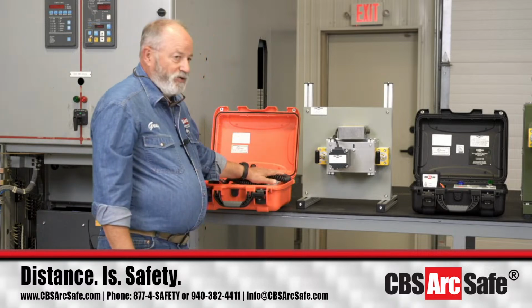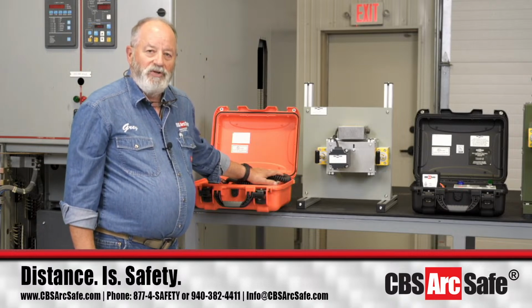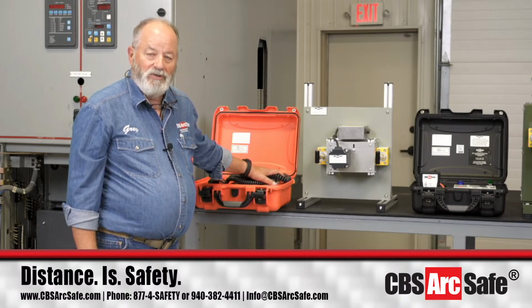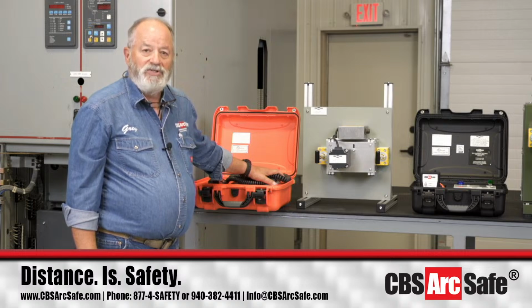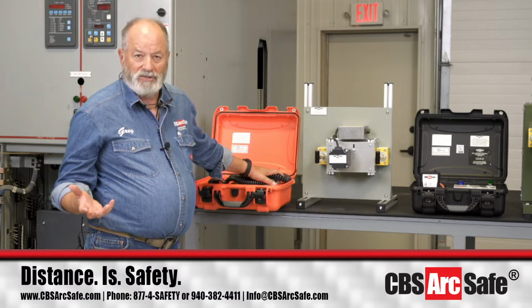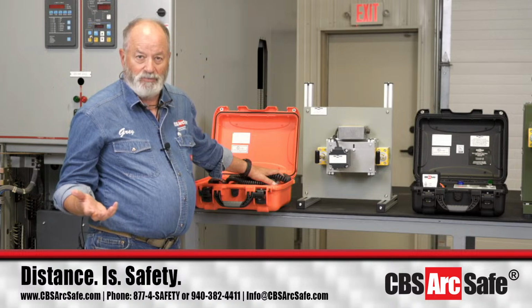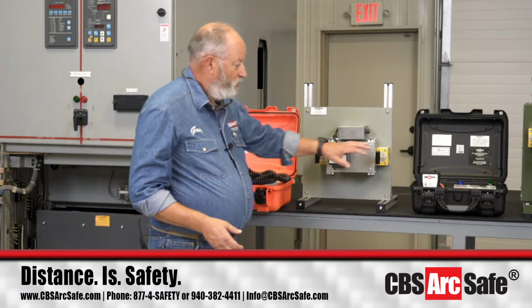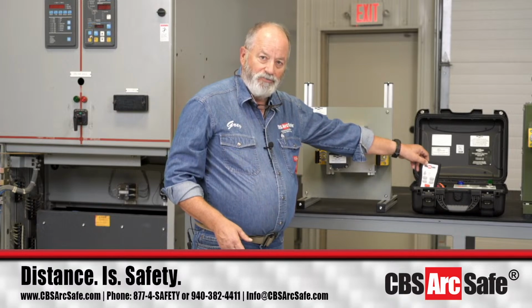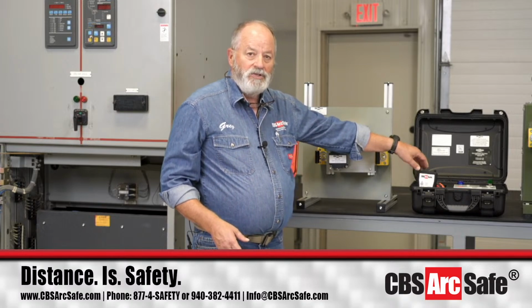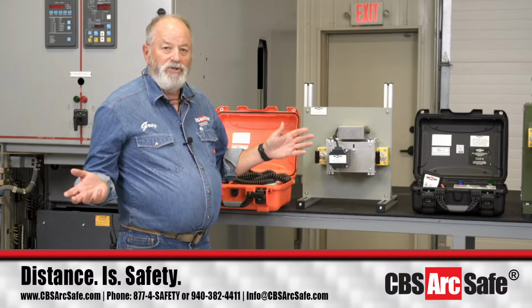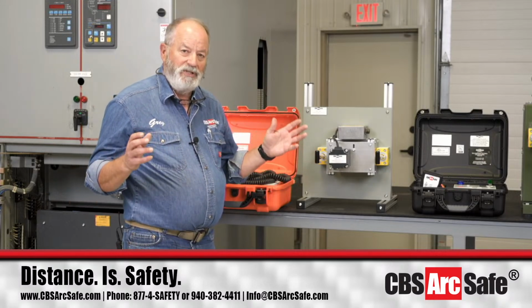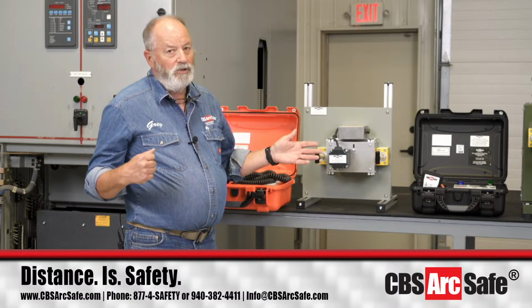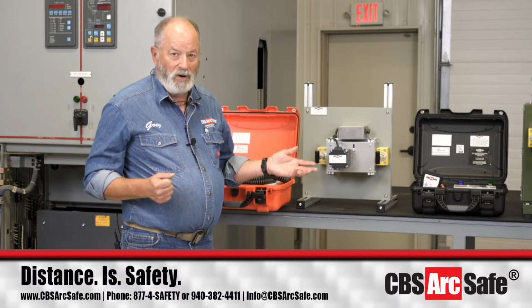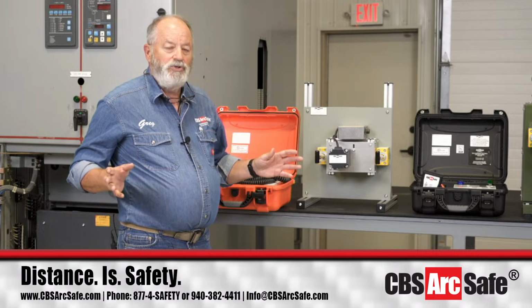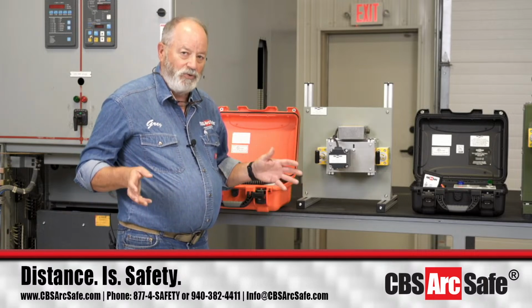Now, on the standard RSO1, we don't have the radio remote. It's an option that we sell to get you outside of the arc flash hazard boundary if you've got something in excess of like 25 feet for an arc flash hazard boundary. It's a similar radio remote to what we have over here on our RSO4, which is standard with that. So if you need a longer distance, whether you need an extension cord or something else, we can do a 25-foot extension cord, or we can do the wireless remote. It all depends upon what your arc flash hazard boundary is that you have to work with.